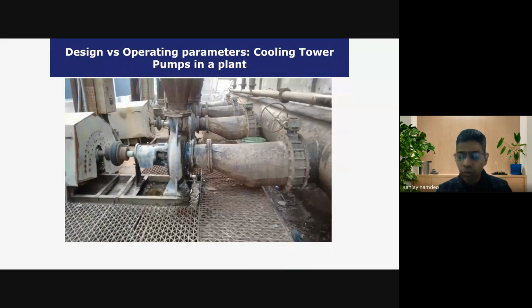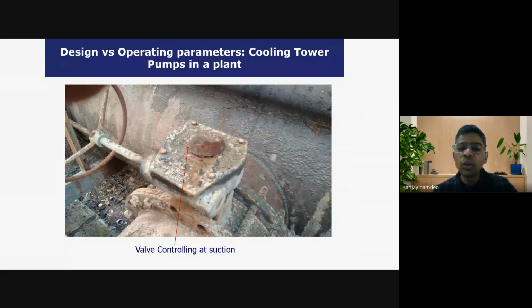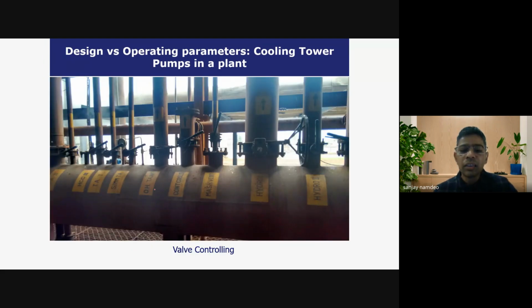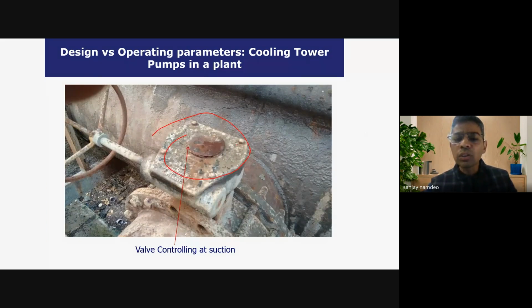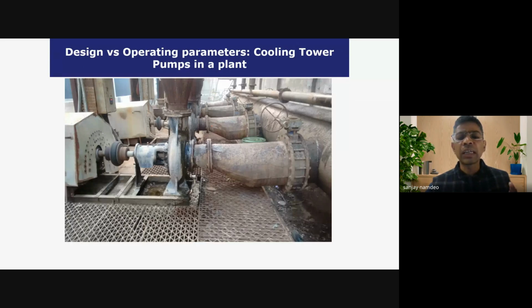Now, during the audit, what we saw is that this pump is being controlled by a throttling valve, and this throttling is done at the suction of the pipe. And the outlet is fed through a common distribution pipe to various users, right? And here also, these are the control valves, right? So when we are controlling the flow by operating the valve, and this suction valve was closed around 80%, a very simple indication: if the pump is being operated by valve control, it means the pump is not correctly designed.